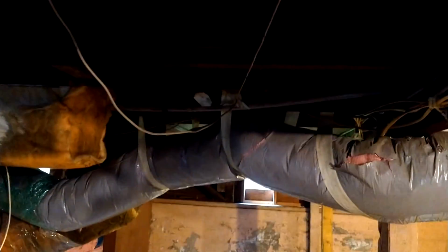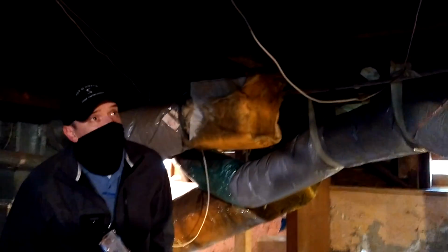Like sagging and dangling should be appropriately, like this wire here that you just had to duck under, Matt, that needs to be tacked up. And it is my belief that it's likely abandoned wire and not in use, and all the abandoned wire was supposed to be removed. Let me see, center room, what we were supposed to look at.